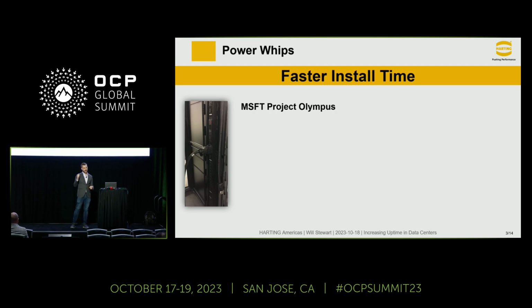What Microsoft figured out with HARTIng's help is that these were two separate problems. The issue of complexity was always tied up in the cable. The amperages just depended on the wire size. The regulations, UL, CSA, et cetera, that was all inside the cable. The facility plug again only applied to the cable. But then it was the rack PDU itself that was the high lead time item.